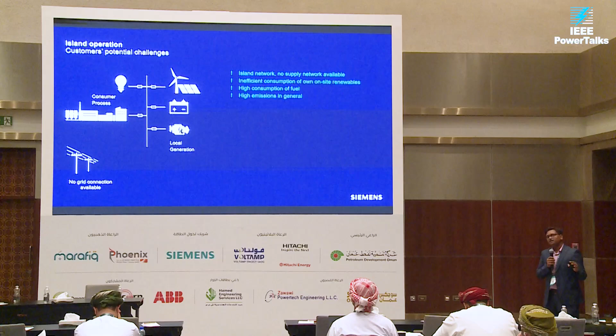But with a microgrid controller, you can fully define behavior: during daytime, whatever power you get from PV, first charge the battery. Once the battery reaches a certain charge level, then serve the load. If you have 3-4 loads, once the battery is fully charged, you can serve the load directly from PV.